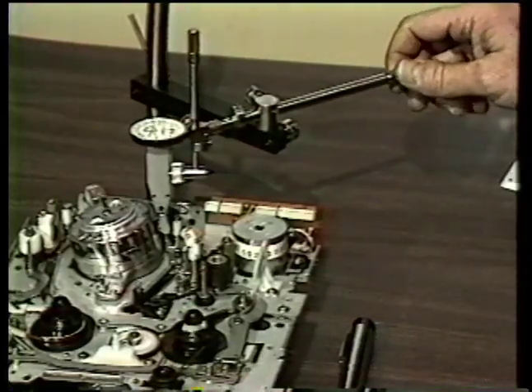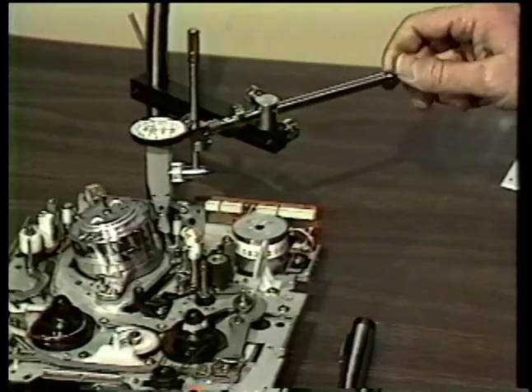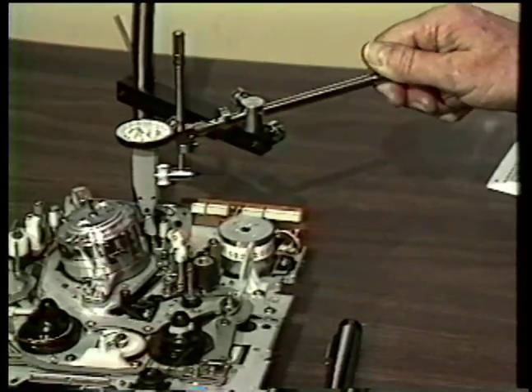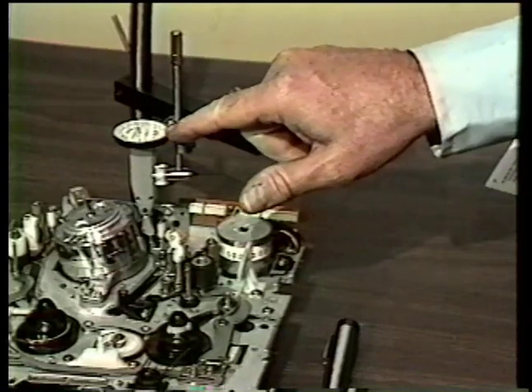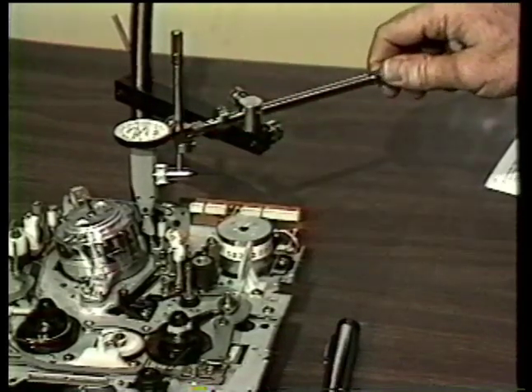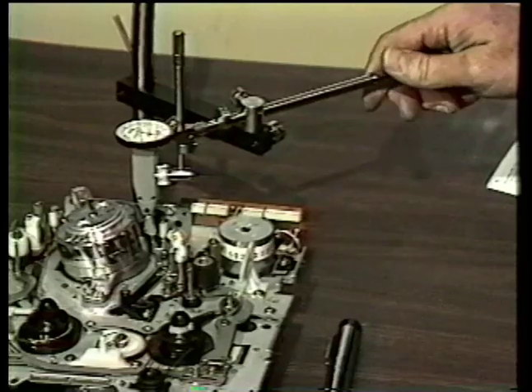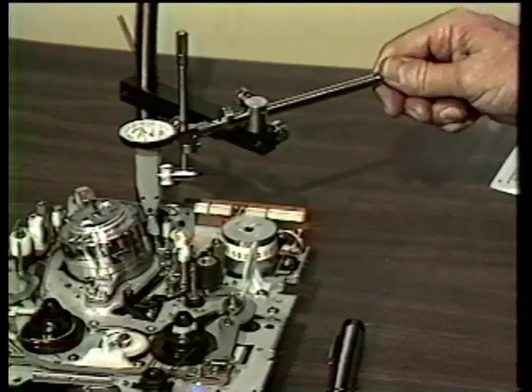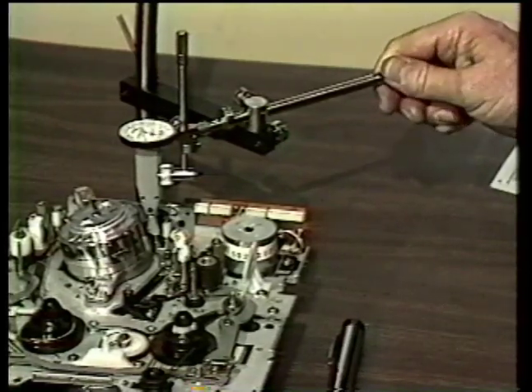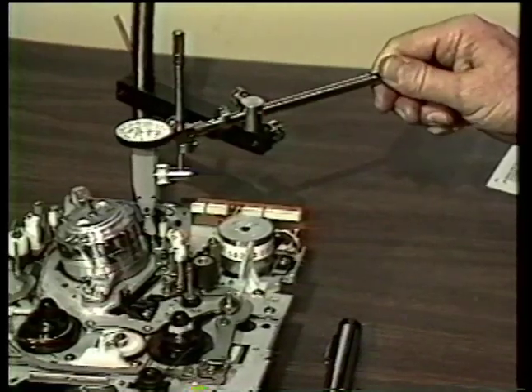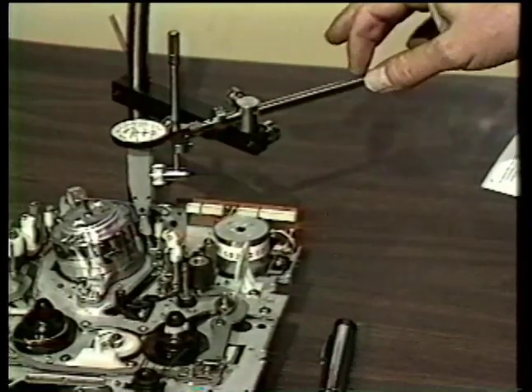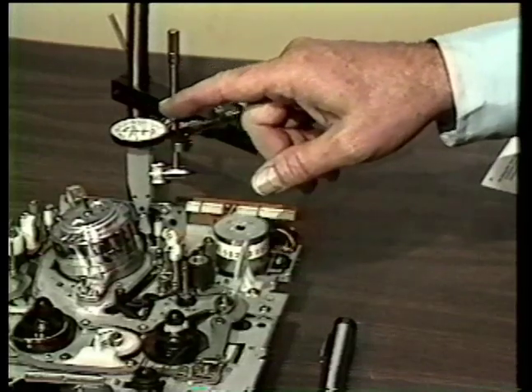We use the horizontal micrometer adjustment to actually engage the tip with the drum, moving the pointer from what's called the rest zone, which is where the pointer rests when it's not touching anything, up to the preload zone. You'll notice that, again, our discussion of microns, 25 microns is 1/1000th of an inch. It doesn't take much motion here to give quite a bit of motion on the indicator.